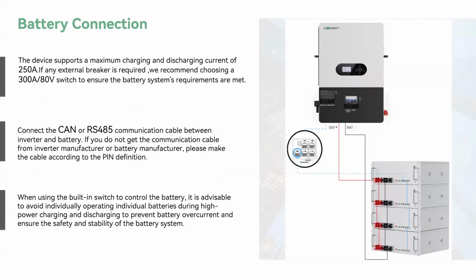As for the battery connection, firstly, for a single inverter, the maximum charging and discharging current is 250 amperes. And if any external breaker is required, we recommend choosing a 300 ampere and 80 volt switch to ensure the battery system's requirements are met. For example, if your battery doesn't have a switch on, you might need to install an external breaker.